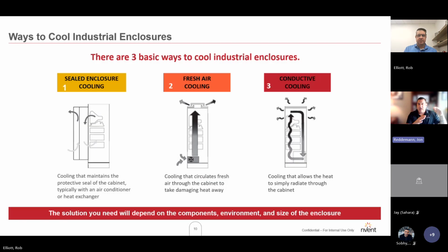The fresh air, let's say we have 75-degree fresh air that we're pushing through an enclosure, the best that we will be able to expect in that enclosure would be 85 degrees, depending on how much air we push through. Conductive cooling, again, approximately that 10-degree delta, depending upon how big we make the enclosure, right?